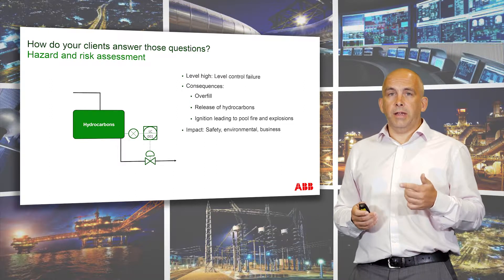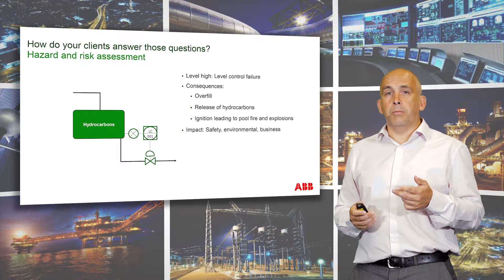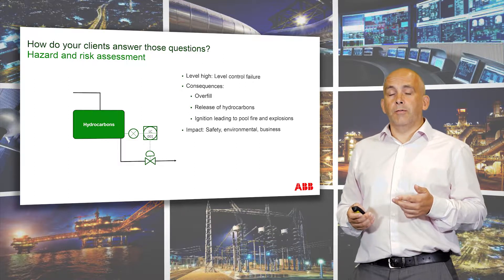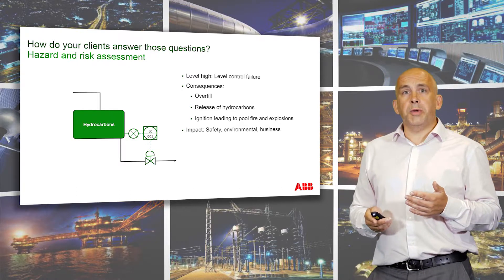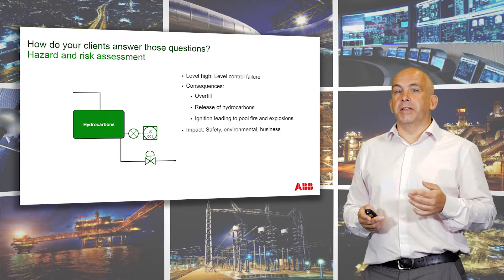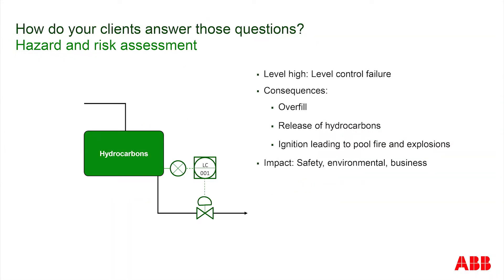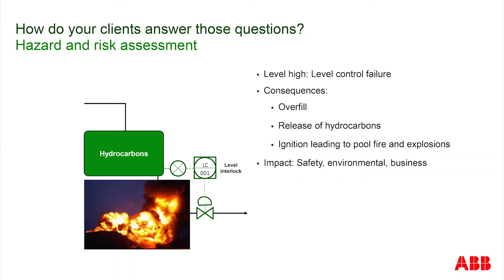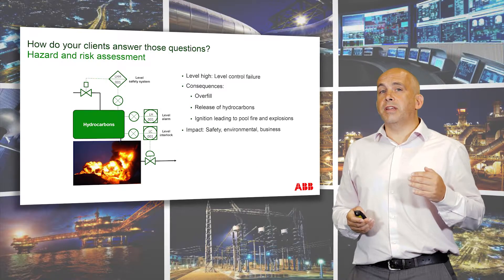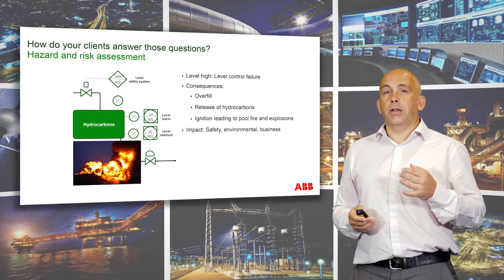That would have safety, environmental and probably financial impacts from that particular event. So obviously we don't want that to happen. We put in place barriers to prevent that. One such barrier could be a level interlock. Another barrier could be a high level alarm — when the level gets high in that vessel, the alarm sounds in the control room. And finally, we have a safety instrumented function: when the level gets ultra high, it closes the feed into that vessel so the level can't get any higher.